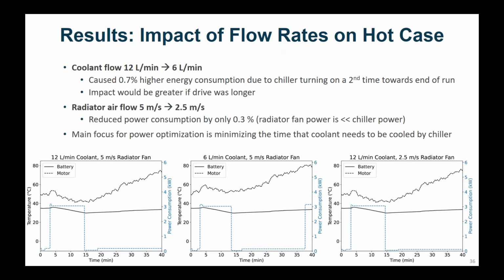We also looked at reducing the radiator airflow from 5 to 2.5 meters per second, so reducing the fan power. But we found that that had a minimal impact on the results and only reduced the power consumption by 0.3%. The radiator fan power is quite small and much smaller than the chiller power. So from this, the main focus for power optimization should be minimizing the time that the coolant needs to be cooled by the chiller.